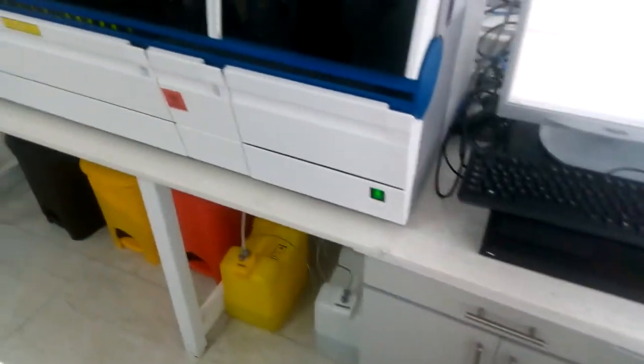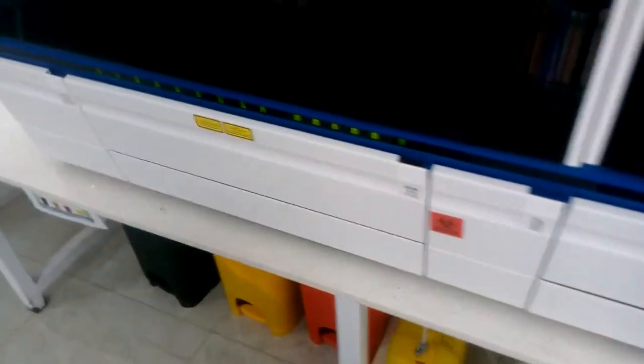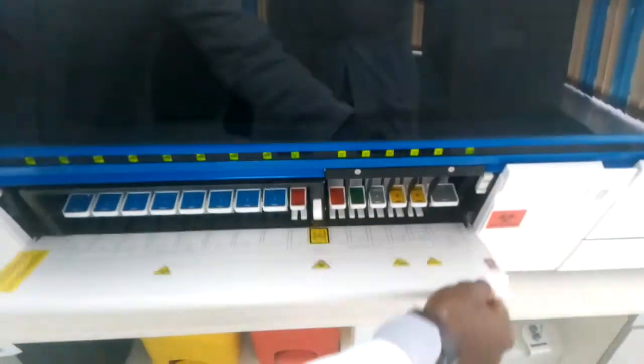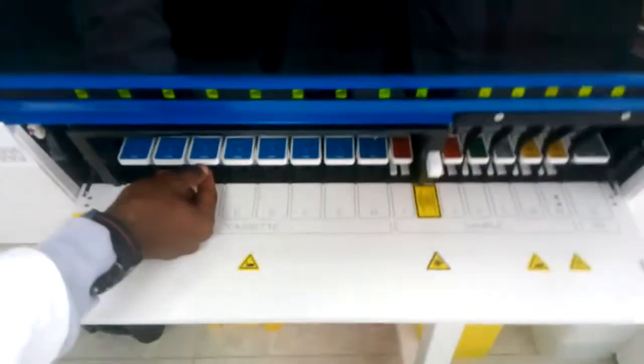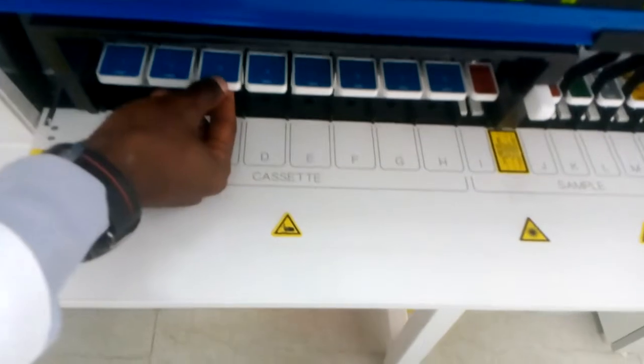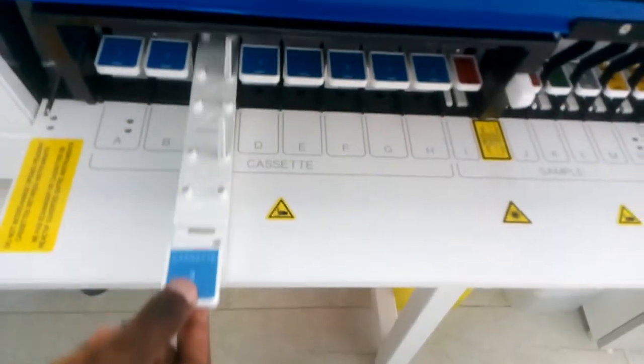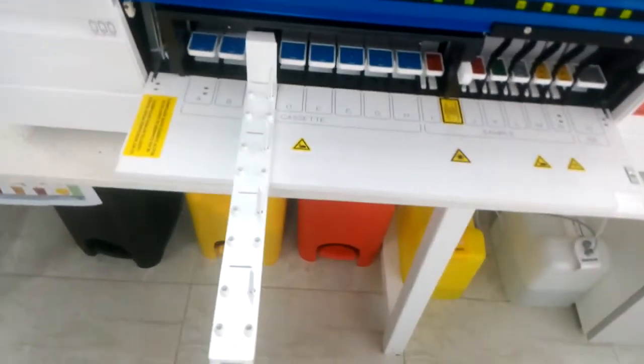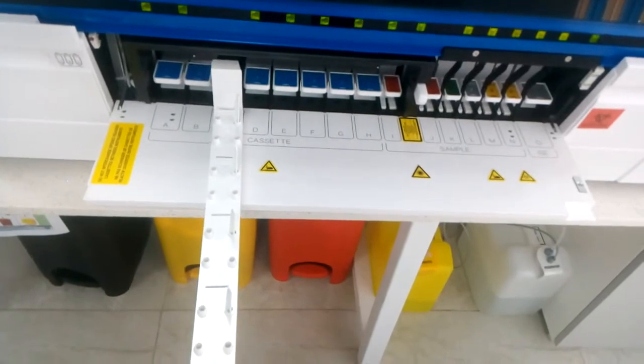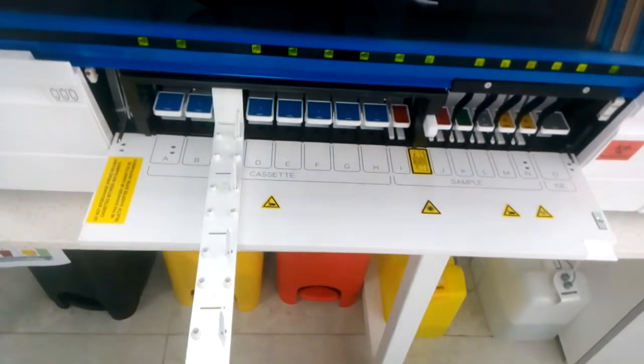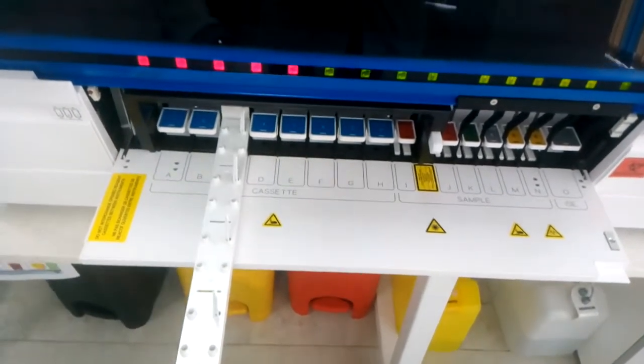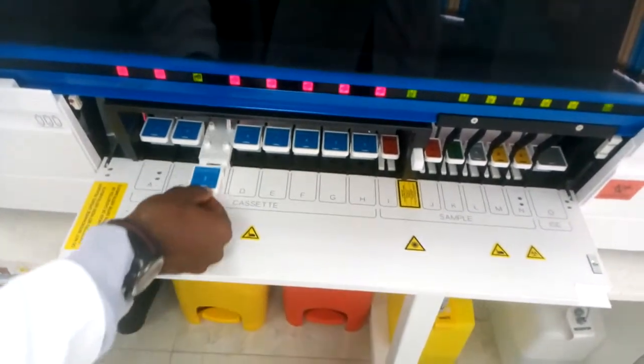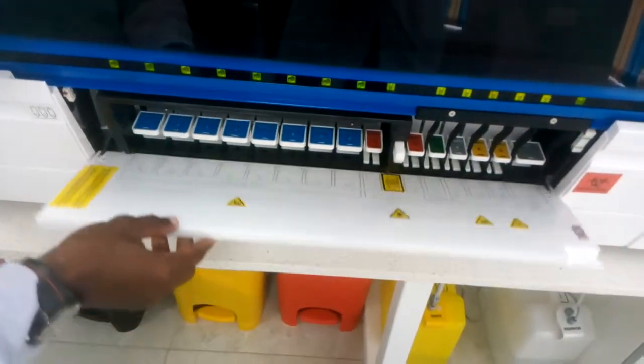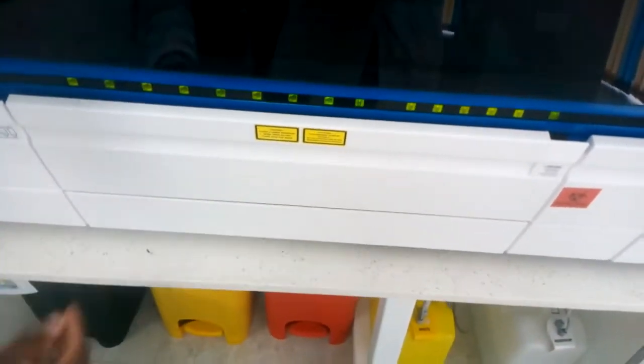So the next thing you need to check is your reagents, to ensure that they are okay and not expired. The reagents are stored in the cassette region. So you pull the racks one by one, checking for expired reagents. But you can also do the same thing by just checking directly on the computer.